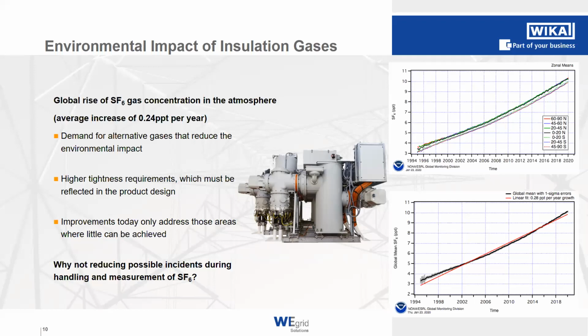So our thinking is, why do we not reduce the possible incidents with handling and the measurement of SF6? And we totally believe that technology can reduce and improve the human impact on the environmental development. And as I already said, we have two main factors with the product design, regarding the tightness. One is the leakage of SF6 gas, and the other thing is that we don't get humidity into our gas. And on the humidity aspect, I will now focus, because that is the point with our GAD unit.